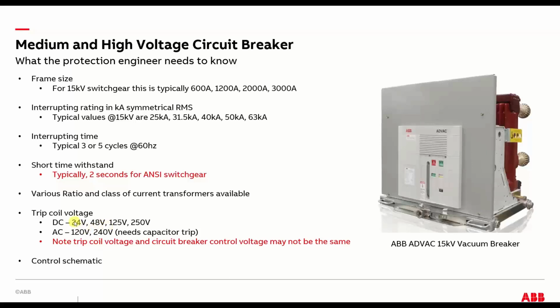And then you should also know what the actual trip coil voltage of the breaker is. And note that the trip coil voltage doesn't have to be the same voltage as any other control in the circuit breaker, like the spring charging mechanism. For example, you tend to want to do your trip coils at DC. So you might have a 48-volt DC trip coil, but then the rest of the system that charges the spring charging motor and does your control and contacts, some of that might be 120-volt AC. So you can easily have mixed voltages in a circuit breaker. It's just something you need to be aware of.